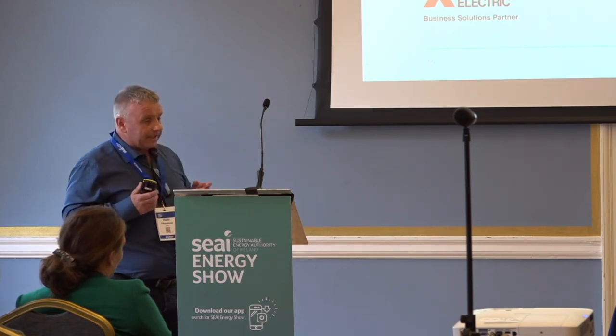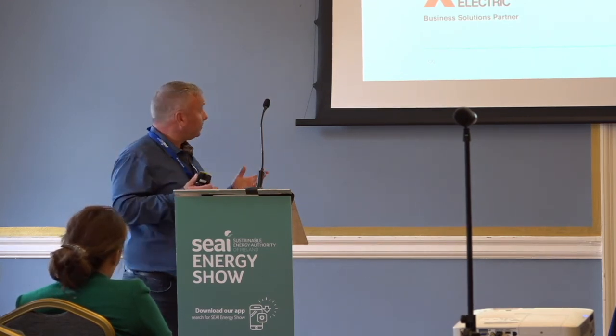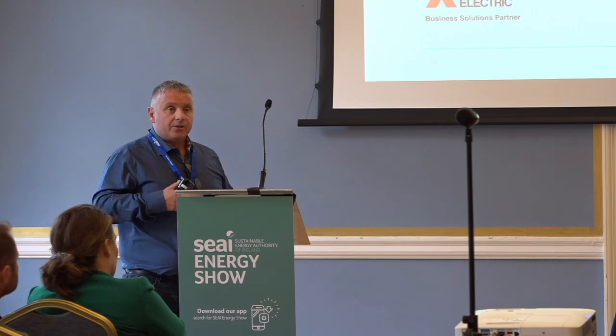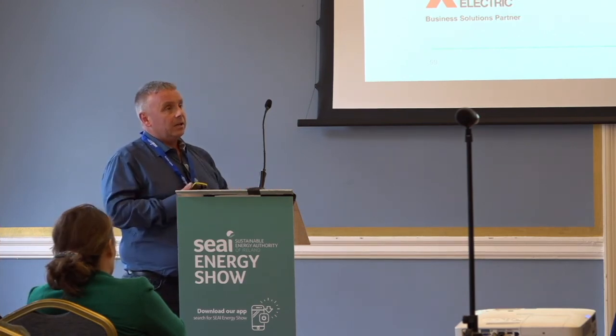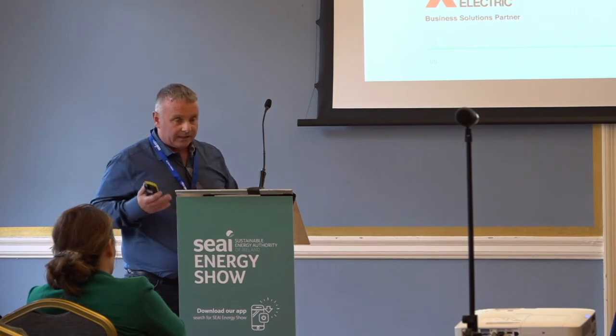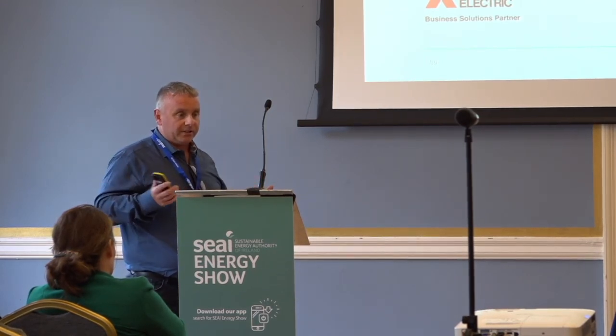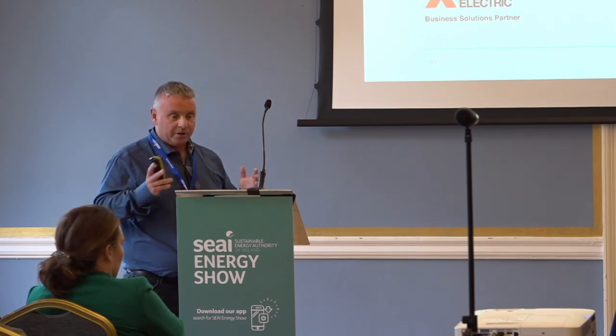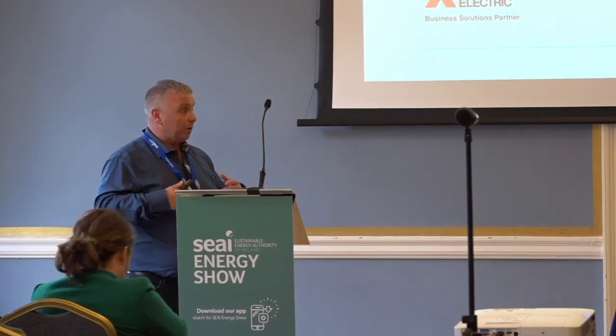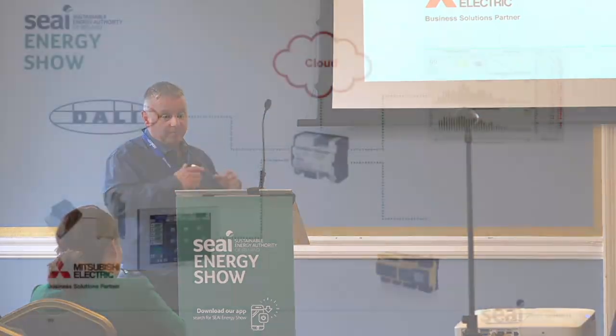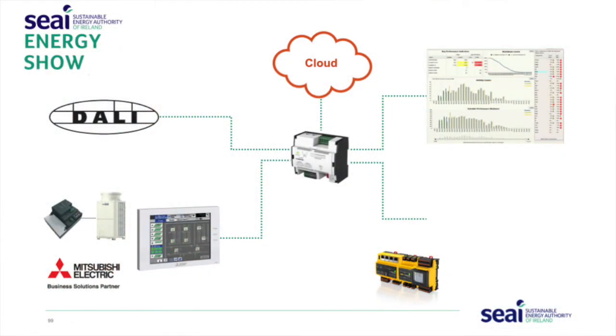This is an example of a job done in the past couple of years, where the building was built between 40 and 50 years ago. Through that lifespan it's had a number of retrofits and multi-tenants on different floors. It started as a conventional LPHW and chilled water distributed system to fan coils, but one tenant came in a few years ago and put in a Mitsubishi VRF system over two floors, which was very popular. Other floors were retrofitted with a new ceiling grid and a whole new lighting system, a DALI system was fitted. But the floors aren't the same - different tenants, but the same management company.